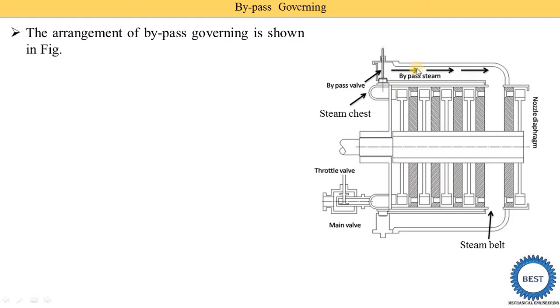Here you see the complete diagram of the bypass governing system. Steam first comes from the boiler and enters the throttle valve, also called the main valve. From the main valve it enters the nozzle, and from there into the fixed blades and moving blades. There is also a bypass valve here, so additional bypass steam is supplied through this bypass valve and mixed with the steam coming out from the high pressure stage.